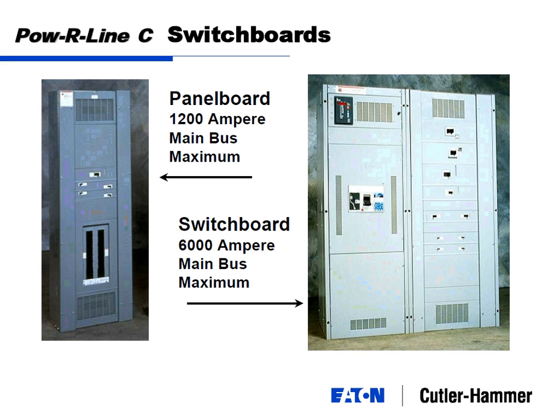Switchboards are big panel boards. Simplified a little bit, but basically this is your power distribution panel board, which tops out at 1200 amps. A switchboard has the ability to go all the way up to 6000 amps. And your panel boards were your wall hanging devices, or at least wall supported devices. Your switchboards are floor mounted devices. So from an installation standpoint, that's the biggest difference.